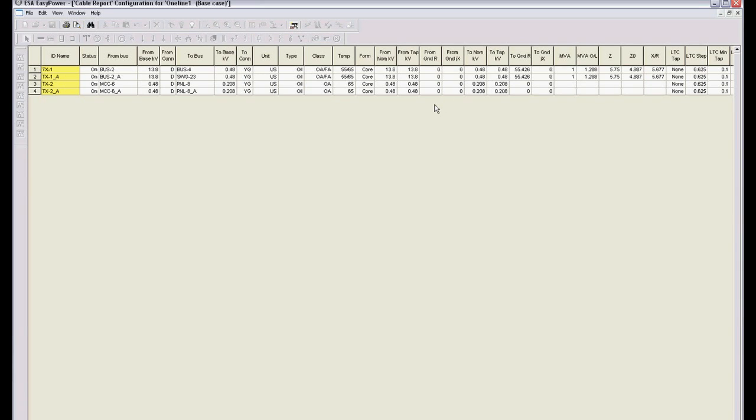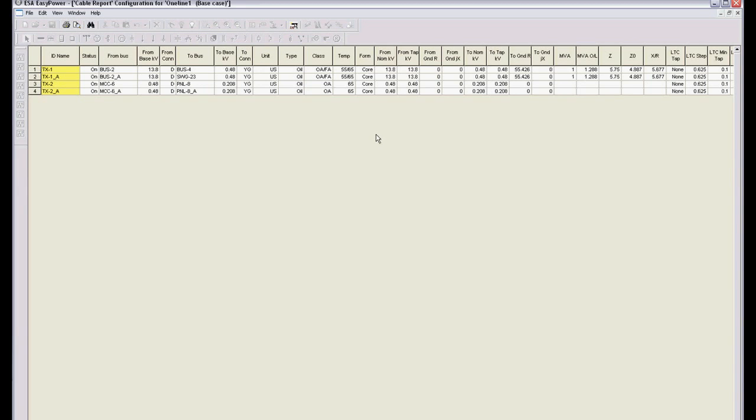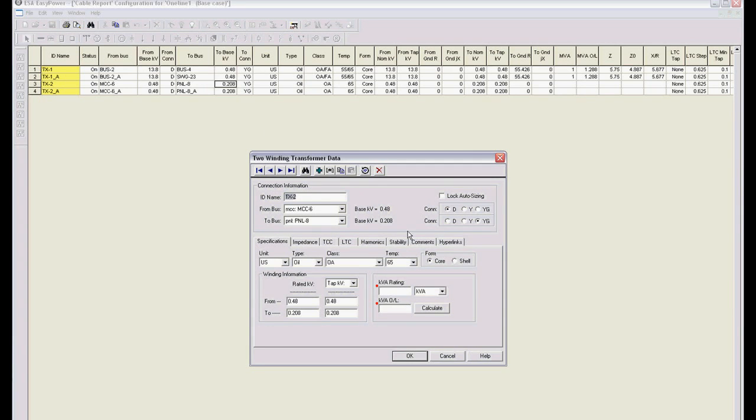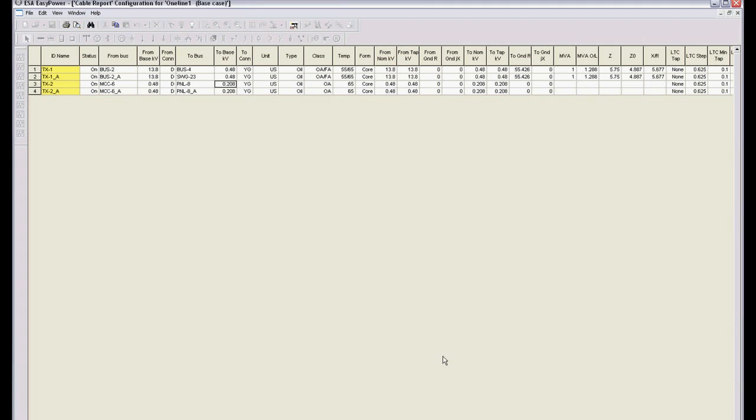We can customize reports that are all column based. So you can have specific named reports for short circuit or power flow or harmonics or arc flash hazard, depending on how you want to report specific jobs. So these can be all custom named reports or you can name them per your client or your own official standards. You can click on any piece of equipment and automatically change it with the dialog box information. All the different equipment is here and available for reporting.